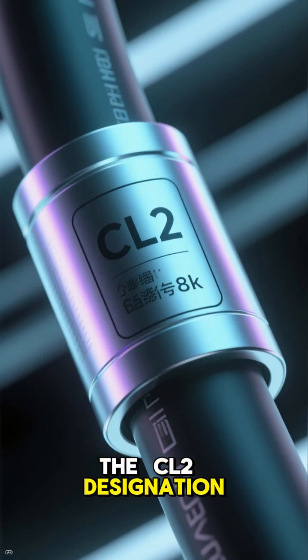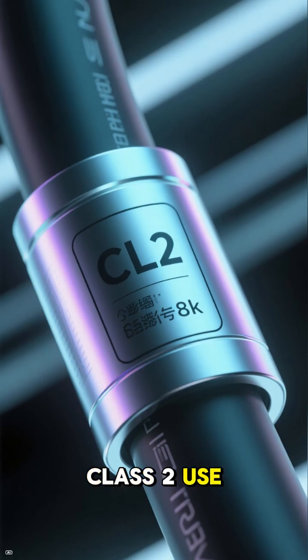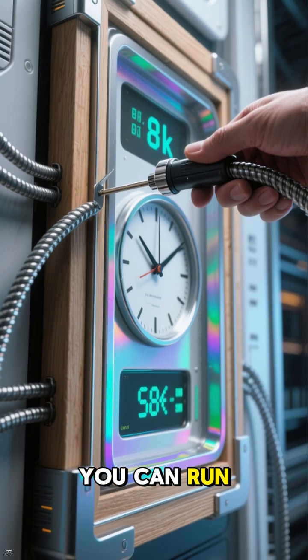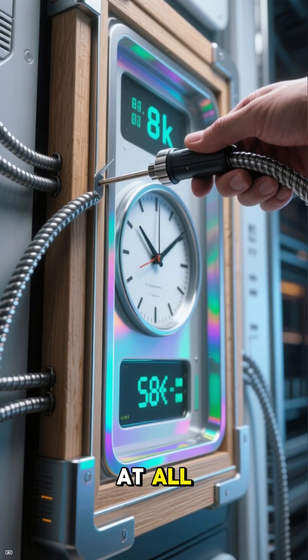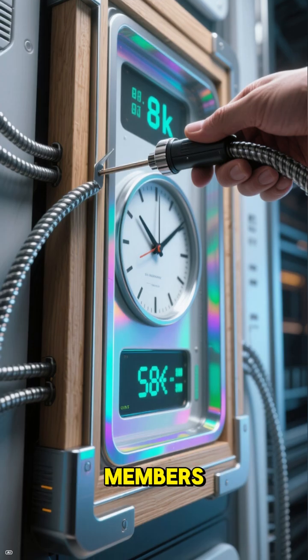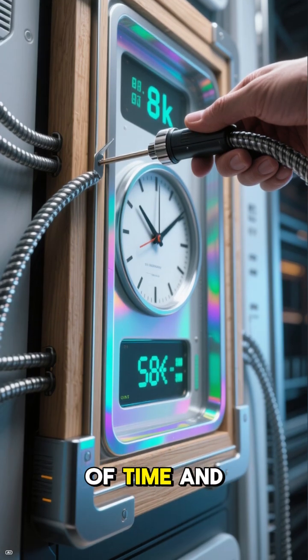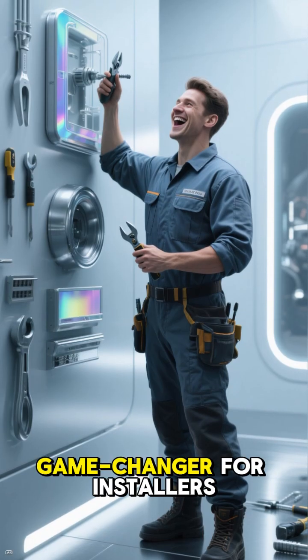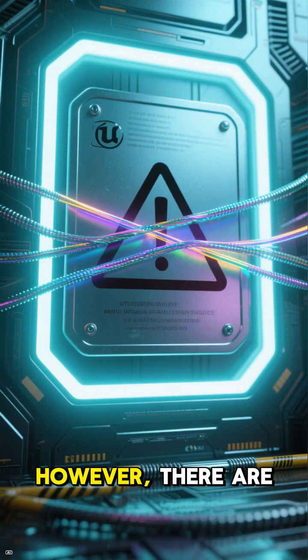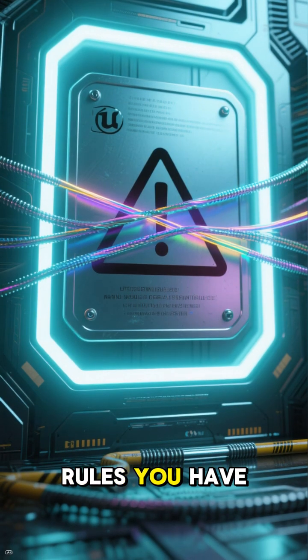The CL2 designation means it's rated for Class 2 use. In many cases, you can run these cables without any conduit at all, stapling them directly to framing members, which saves a massive amount of time and material. This is a game changer for installers. However, there are still very important rules you have to follow.